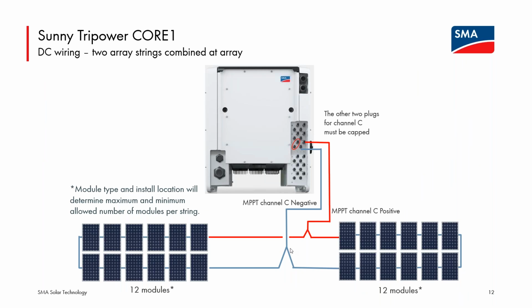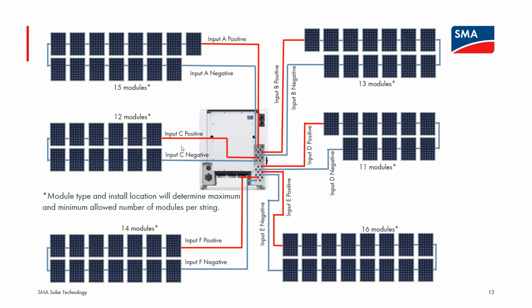We're showing kind of that Y branch connector here. So we'd have something we would expect, similar string length, similar orientation, combining the positives and negatives to bring a single positive and negative for that channel back to the inverter and simply cap the other positive and negative. But you do have that flexibility for potentially 6 different string lengths, 6 different orientations. And again, each of these tracking channels is being operated independently. These could be different module types. As long as you are remaining within that 150 up to 1,000 volt DC operating window, the inverter will be making power from each of these 6 tracking channels, and it's operating them all independently.